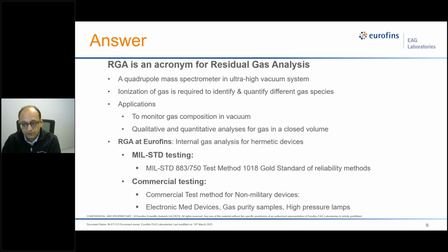You can use the high resolution mass spectrometers for qualitative and quantitative analysis, the one that we have for the RGA setup at our EAG laboratories. This particular RGA is designed to do internal gas analysis for hermetic devices. The meaning of hermetic device is that it has a sealed cavity, so there is some kind of a gas environment or sometimes a vacuum inside the cavity. And we want to confirm or investigate what is the gas inside this cavity. That's why this RGA system is developed, where we can extract the gas from the cavity and look at their composition, identify and quantify these gases.